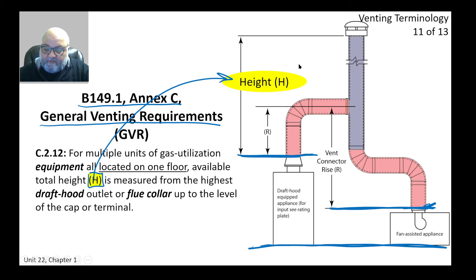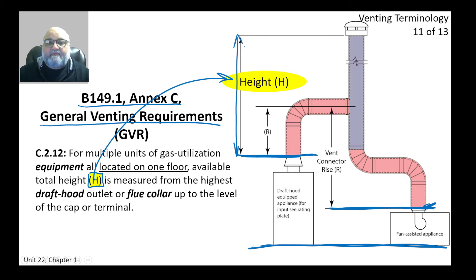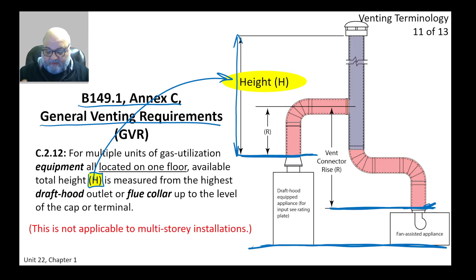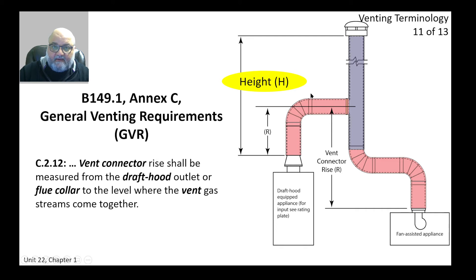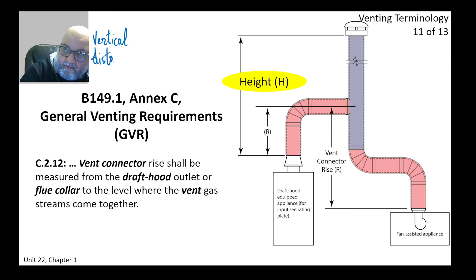Height is measured up to the level of the cap or terminal. This can be a source of confusion — knowing where to start measuring. This does not apply to multi-story installations. Also remember: the vertical distance is called 'height' only for the main vent.